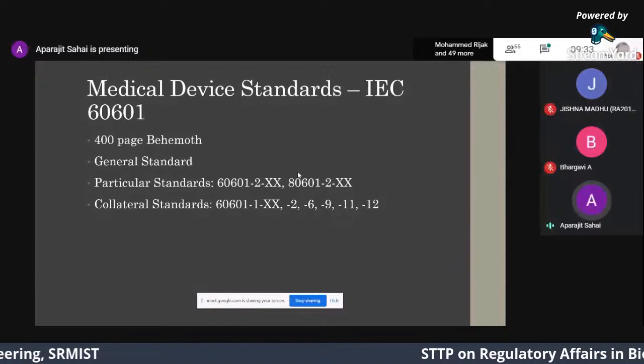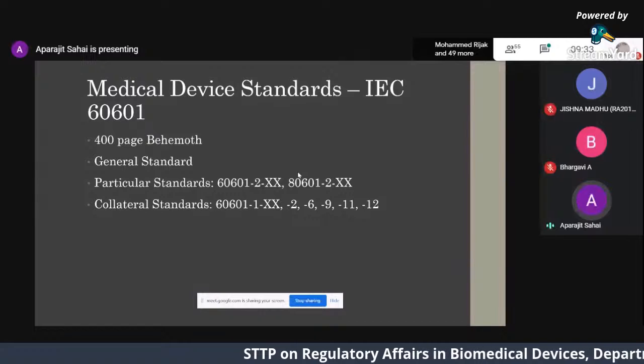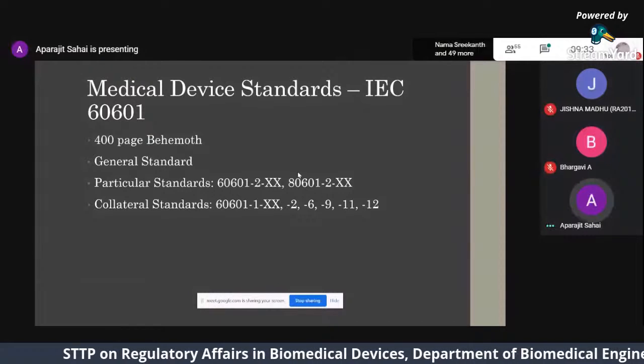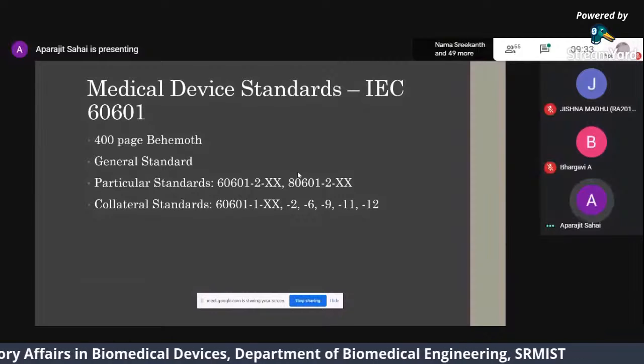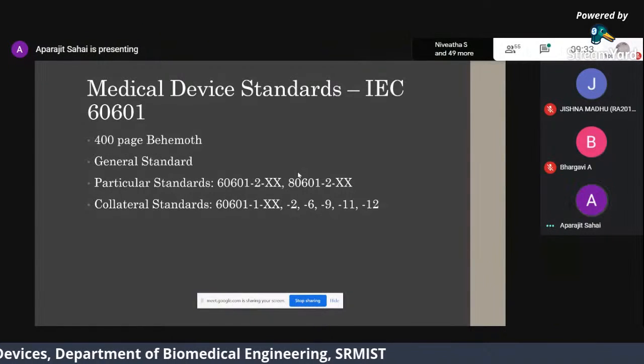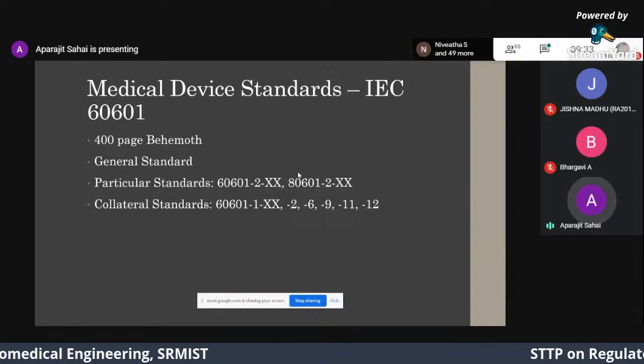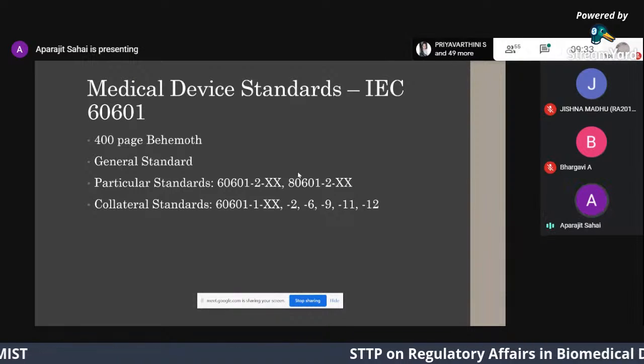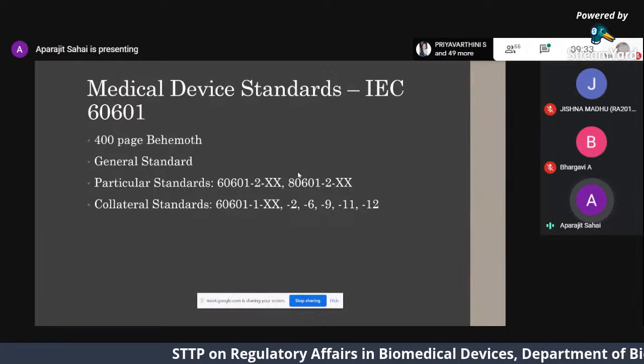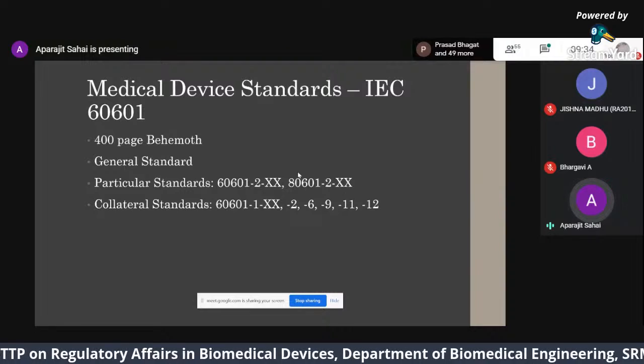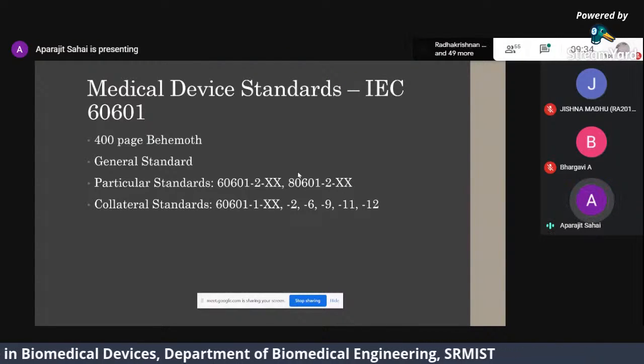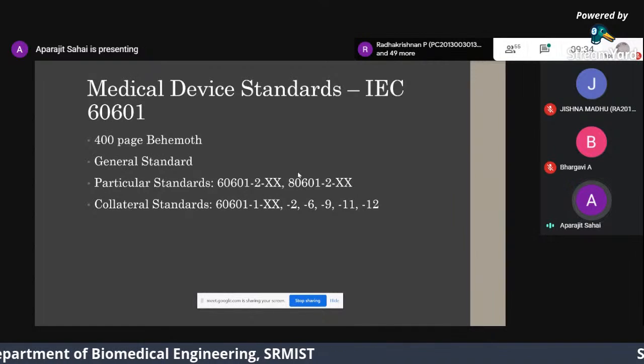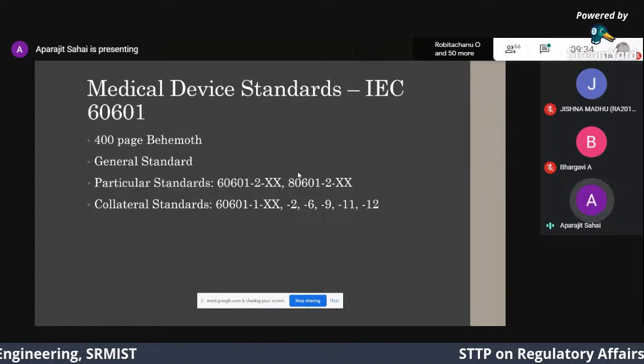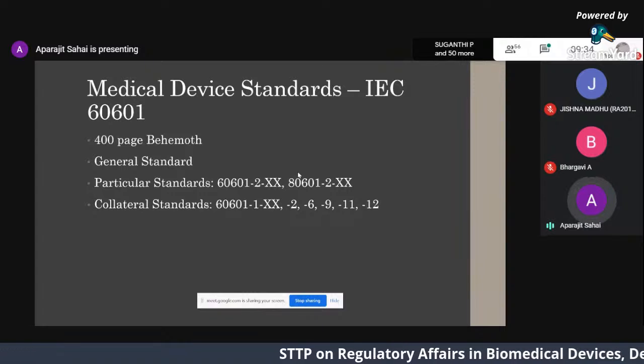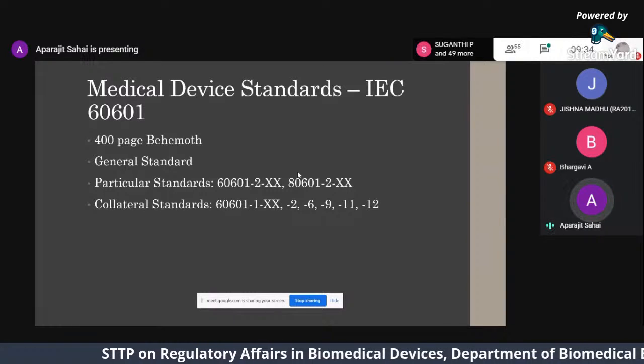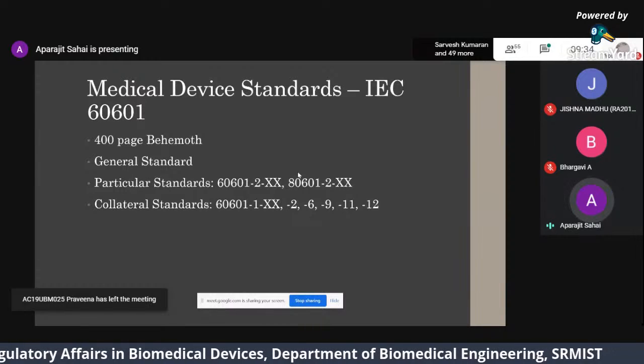So there's immunity, which is how well you prevent external electromagnetic radiation from interfering with your device. And then there's emissions, which I was forgetting the term for, but essentially it's how good your device is at not radiating electromagnetic energy that would interfere with others. So there are levels defined within the standard. There's also ESD. A lot of times with electronic and electromedical devices, static charge can kill the device. So ESD testing is very important, and there are specific levels that you need to test at based on the application and the materials that are on the surface of the device.